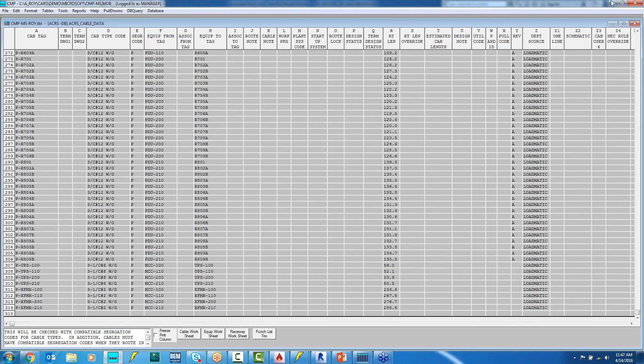So this is our cable schedule input form, and we have defined and created 314 cables for this particular project. So going back to this, if we take a look at these medium voltage cables, let's go ahead and route those cables, and then the program will show us how the cable was routed through the raceway. This is not actually a Revit conduit.